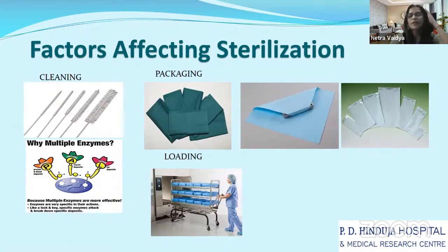Now loading is another important factor in terms of sterilization. The picture which I have captured is from an abroad sterilization method, showing how you stack your items. You should not stack them too tight. There should be a gap between each pack, so that your steam penetrates, your air removal is easy, and the end result is that you get everything sterile. You cannot jam everything into the sterilizer, as that will end up in wet packs, which again is a cause of concern in terms of sterility.